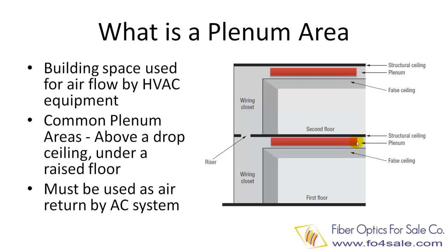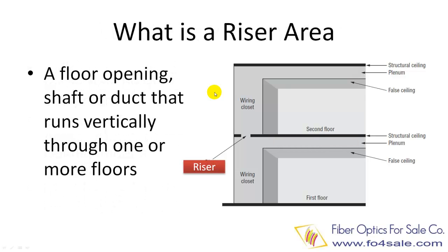In most buildings, the area above a drop ceiling or under a raised floor can be a plenum area, but only when they are used by the air conditioning system for air return. If it is not used for air return, then it is not a plenum area. The picture shows where plenum areas typically are. Now let's check what is a riser area. The riser area is a vertical shaft used to pass cable between two floors, as shown in this picture.